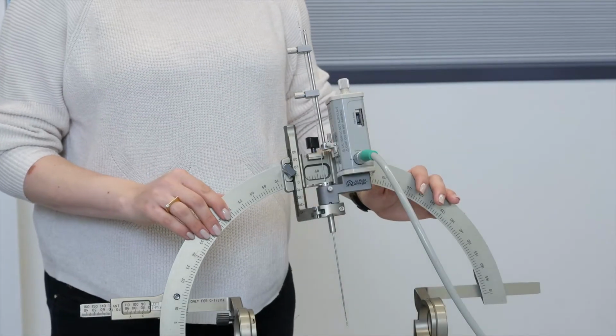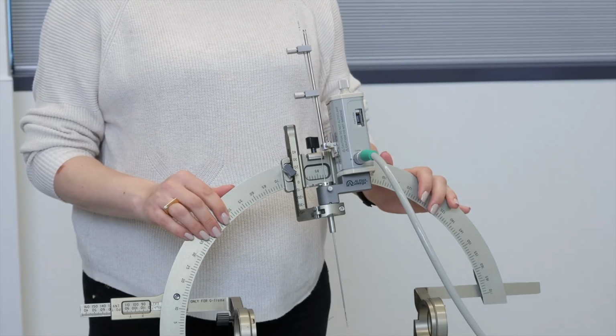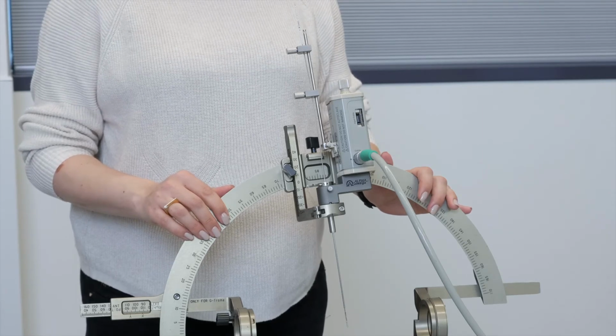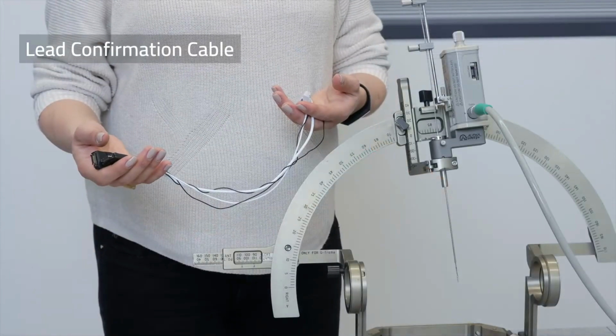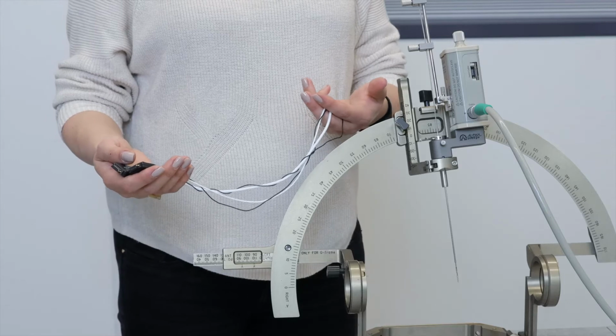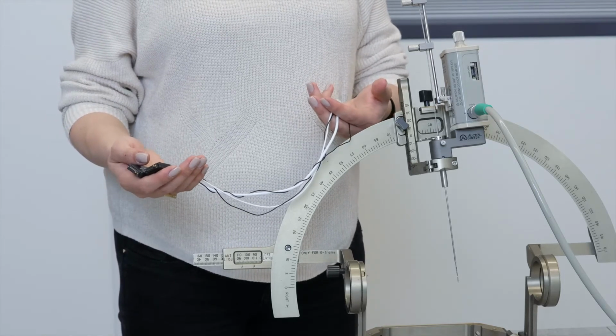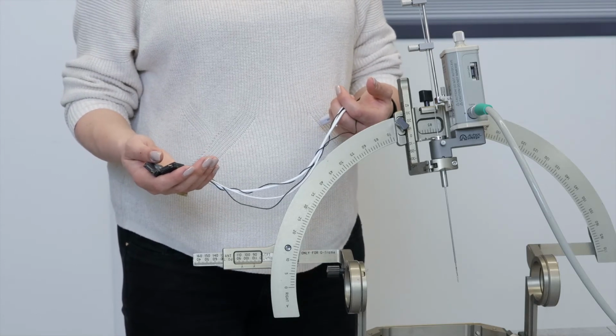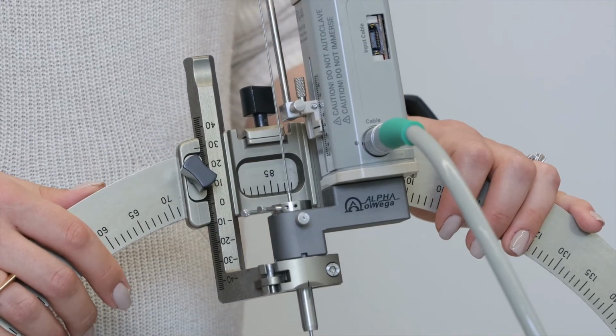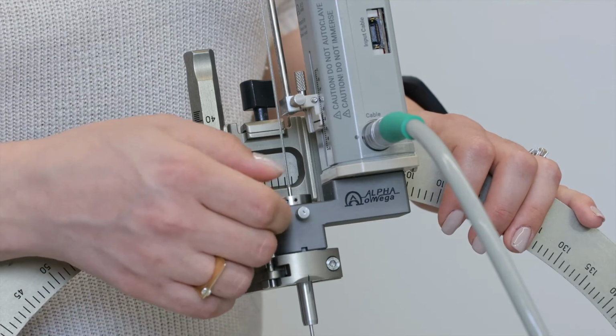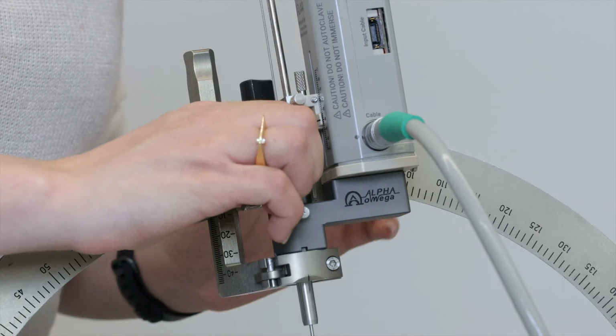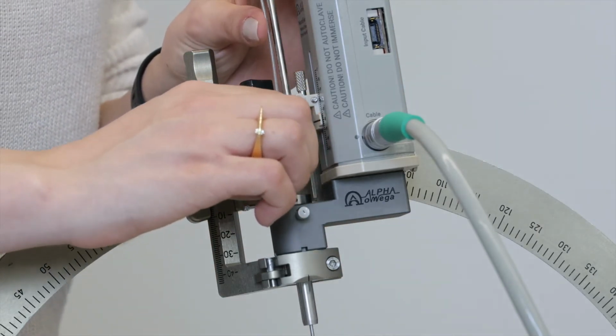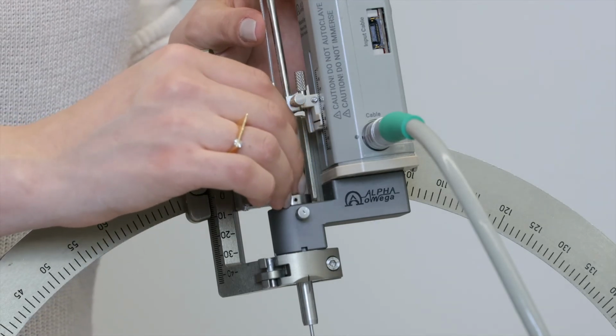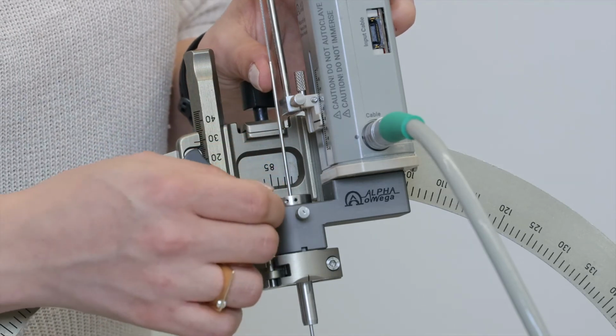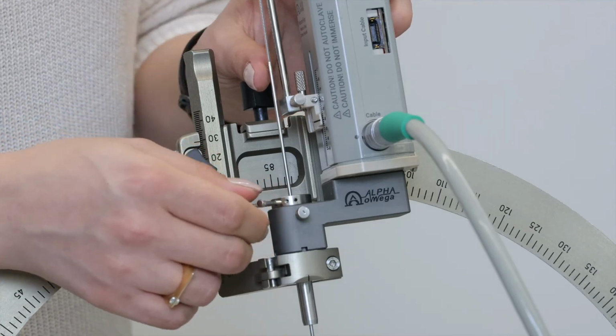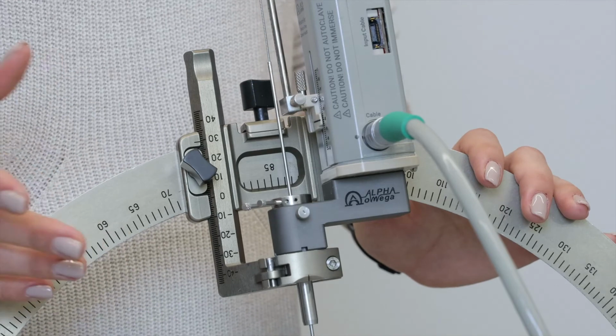For verifying purposes, some of our healthcare providers take a picture using fluoroscopy or O-arm, verifying that the DBS contact has been implanted where desired. For better DBS lead confirmation, Alpha Omega has created the Lead Confirm cable to allow recording from leading types of DBS leads available on the market. To secure the DBS lead, unscrew the cannula screw and carefully retract the cannula. Once the DBS lead is visible, secure the cannula using the screw and the DBS lead using the stem lock or other methods.